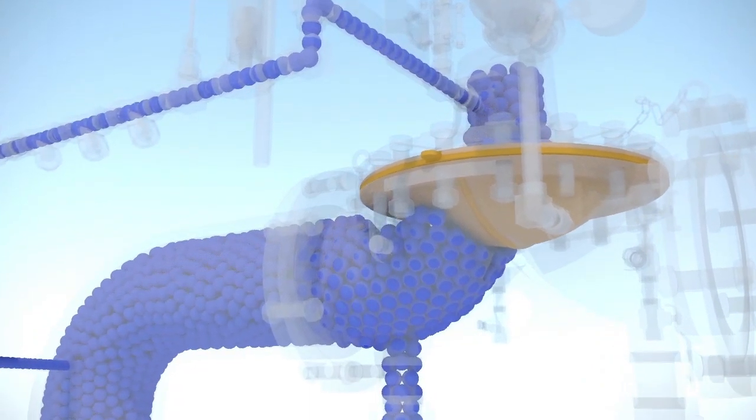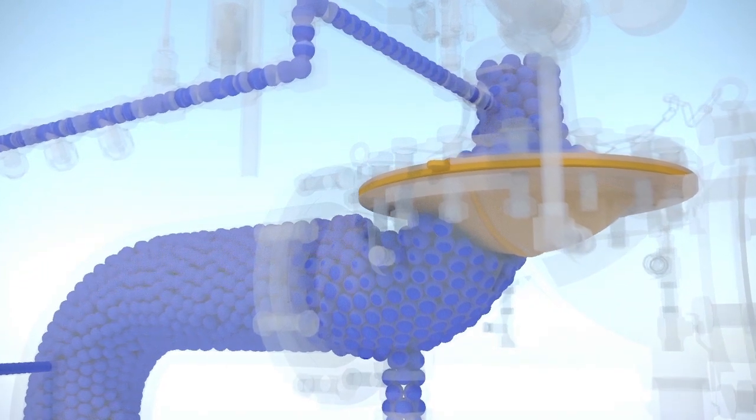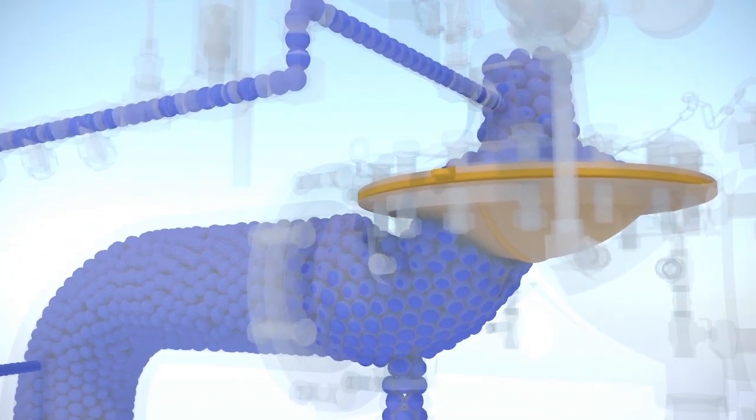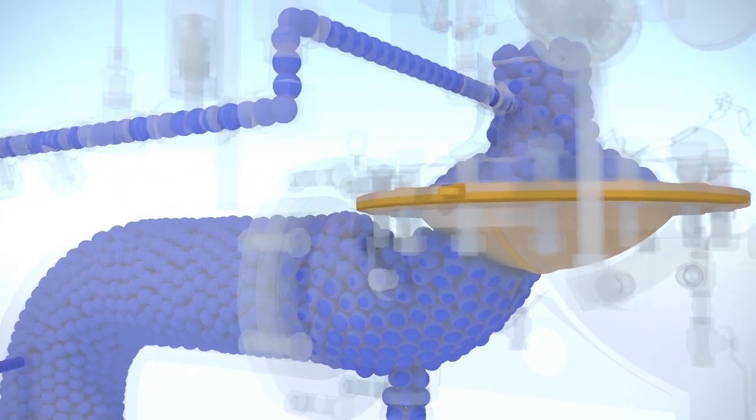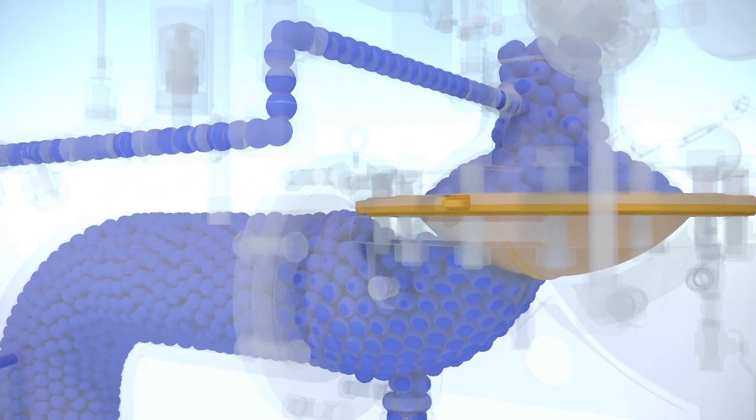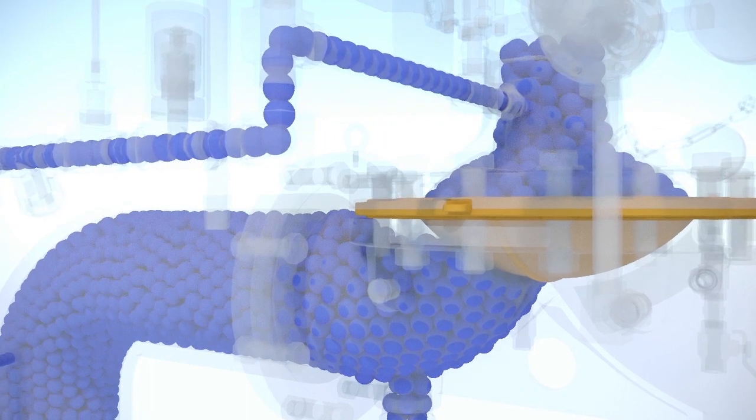In order to keep the valve closed, the same water from the main is used to fill the priming chamber. Besides the water being at the same pressure, the difference in the surface contact between the priming chamber and the lower diaphragm will keep the valve closed tightly.